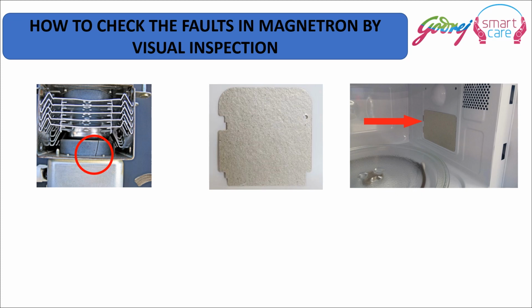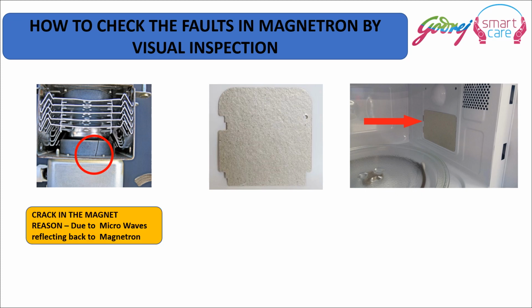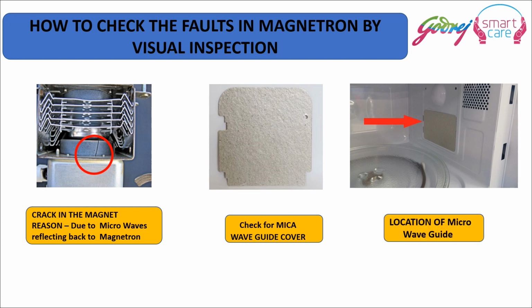Other problems that can occur with the magnetron are if the magnet is cracked, where it is shown over here with a red circle, and there is a mica filter paper which is placed just below or in front of the magnetron, and this paper, if it is broken or burnt or cracked, then also there is a problem of the magnetron getting defective because of this. Check for cracks in the magnet, check the waveguide cover whether it is burnt or browned or blackened or cracked or torn. All this will indicate that there has been some kind of misuse which has resulted in damage.